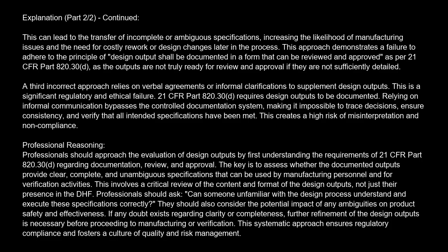A third incorrect approach relies on verbal agreements or informal clarifications to supplement design outputs. This is a significant regulatory and ethical failure. 21 CFR Part 820.30(d) requires design outputs to be documented. Relying on informal communication bypasses the controlled documentation system, making it impossible to trace decisions, ensure consistency, and verify that all intended specifications have been met. This creates a high risk of misinterpretation and non-compliance.